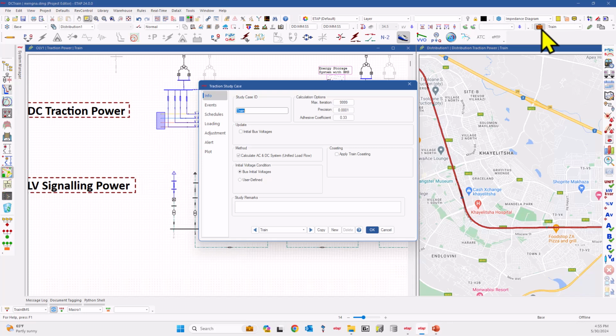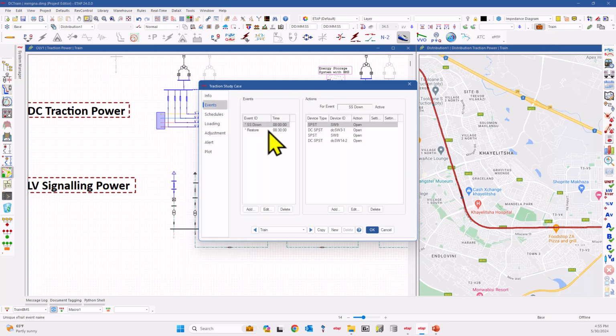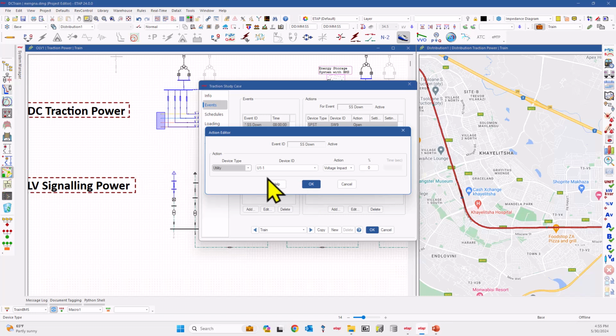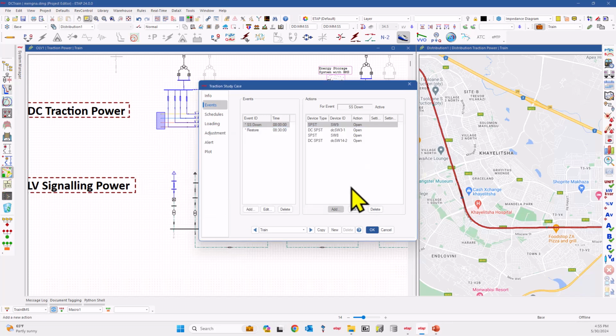The events can be set in the traction study case. In the events, you can define at a specific time what the event ID is and add different types of events to the system, such as opening and closing certain protective devices, voltage variations of the utilities, variations of loads, etc. This is of great help if you do contingency analysis.